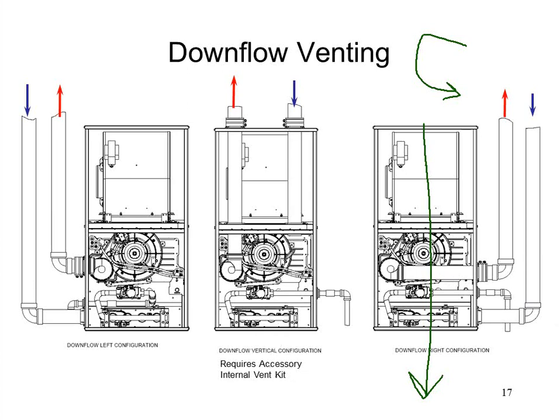But I could run it through the blower housing if I want to. I would generally recommend not doing that for two reasons. One, running combustion air through my regular airflow assembly sounds like not a good idea to me. And two, more practically speaking, it blocks my access to the circuit board and the blowers. But if for some reason you need to do this, you got a really tight closet and you want to have downflow air running through this guy and you can't vent out the left or right and you got to vent back out the top or the bottom as it is now, you can't do that. You got to get an accessory internal venting kit, and then that basically comes with the little penetration grommets to seal those up so that way you can have a full continuous pipe going through your blower housing without having to worry about air leaking through there.